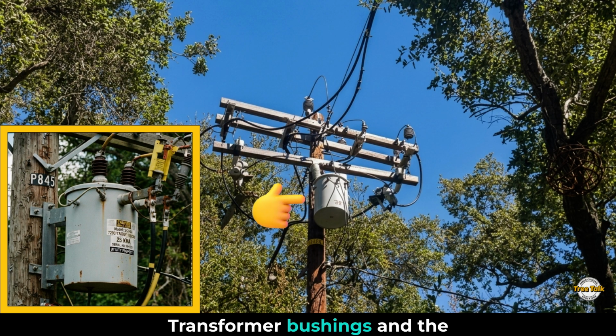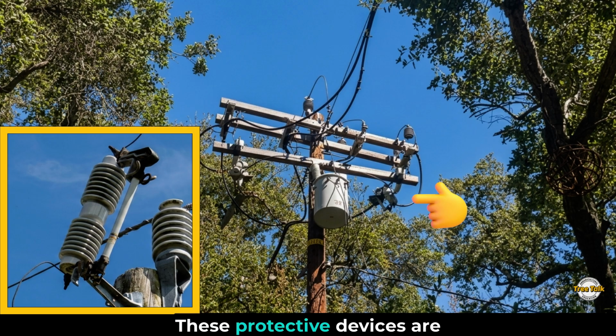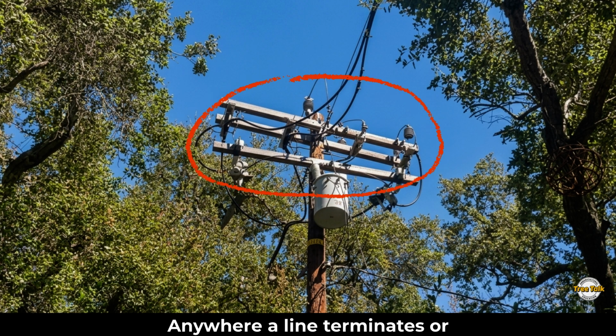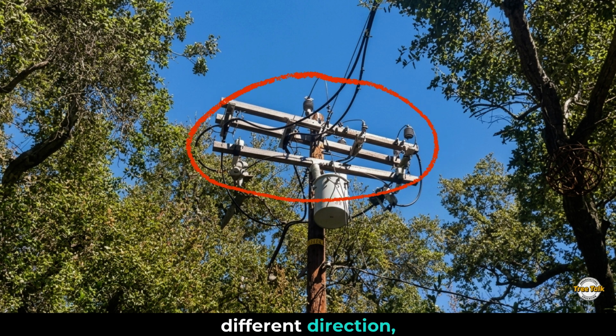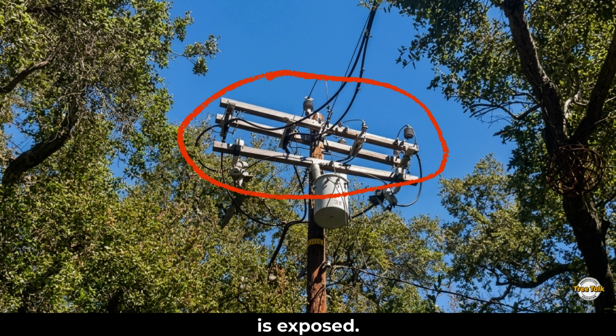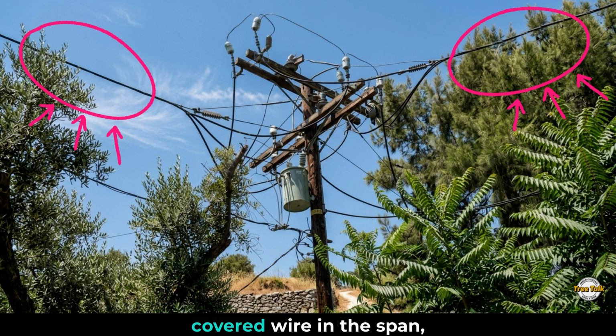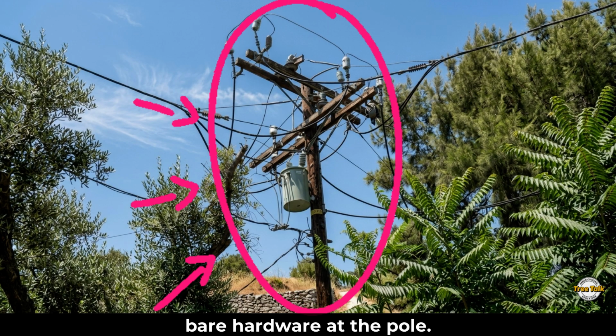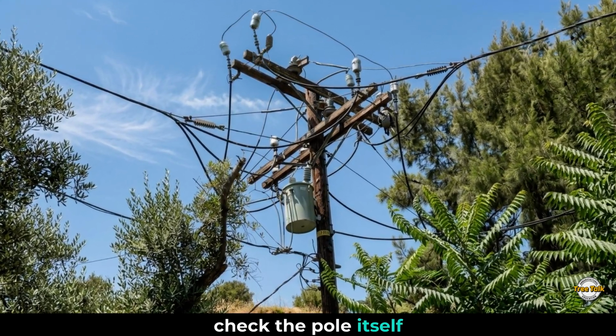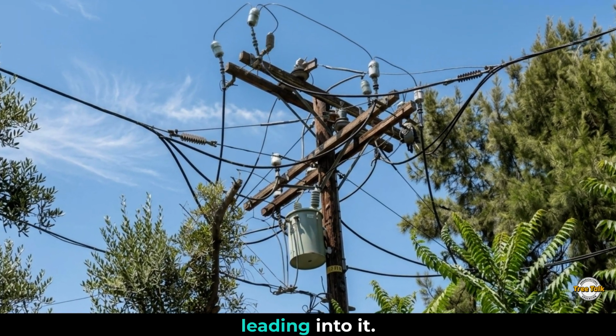Transformers. Transformer bushings and the connections leading into them are exposed. A transformer sitting close to canopy growth is one of the highest priority checks on this whole list. Cutouts and fuses. These protective devices are mounted with exposed conductive parts and are easy to overlook if your eye is drawn to the covered wire instead of the equipment around it. Dead end and tap hardware. Anywhere a line terminates or splits off to serve a different direction, the hardware at that junction is exposed. The pattern across almost all of these: covered wire in the span, bare hardware at the pole. Train your eye to specifically check the pole itself as its own zone, separate from the span leading into it.